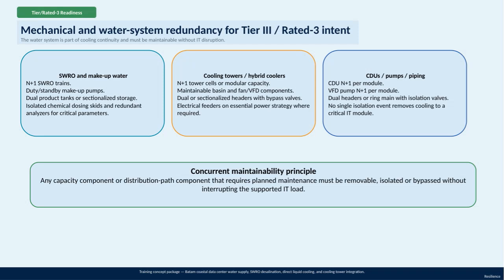Let's dive into the Tier or Rated 3 readiness, focusing specifically on mechanical and water system redundancy. For a Tier 3 data center, maintaining continuous cooling is critical, and that includes the water system, which must be serviceable without causing any disruption to the IT equipment. First, regarding resilience, the training concept package covers Batam's coastal data center water supply, which integrates SWRO desalination, direct liquid cooling, and cooling towers. This approach ensures a robust and reliable cooling process.